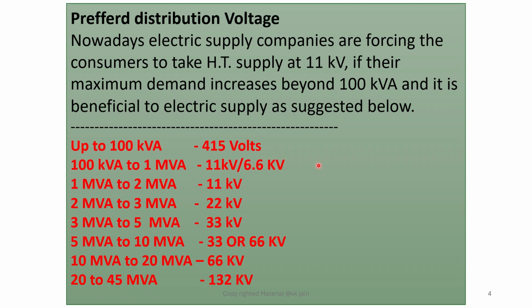Friends, this slide provides the preferred range of distribution voltages depending upon different loads, from 100 kVA up to 45 MVA. Nowadays, electric supply companies are forcing consumers to take HT supply at 11 kV if their maximum demand increases beyond 100 kVA, and it is beneficial to the electric supply as suggested below.